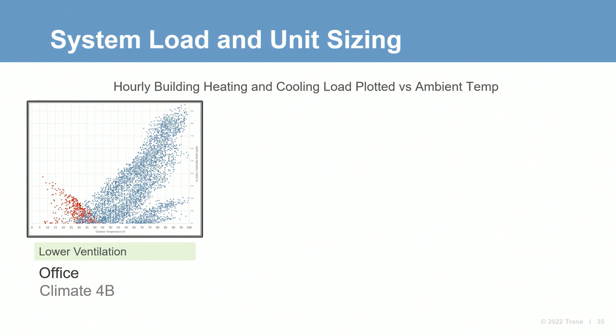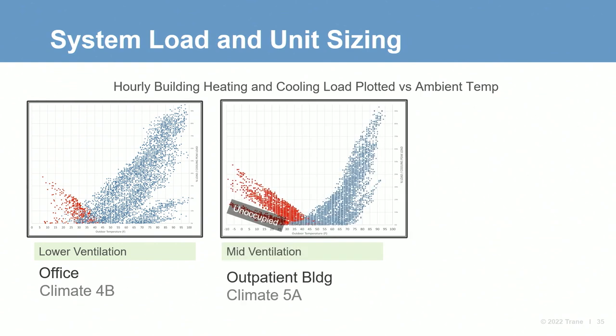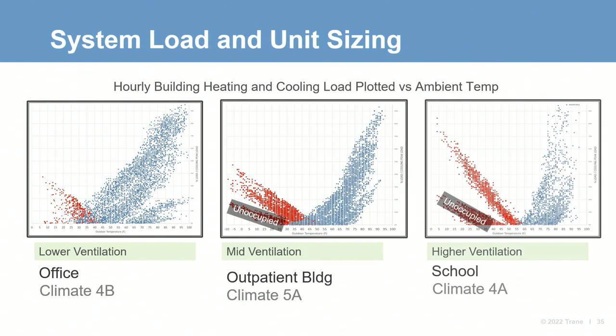Now, let's bring in different building types with different ventilation rates and climate zones and then compare. We'll look at an office building in climate zone 4B, an outpatient building in climate zone 5A, and the school from our first example. First, notice the variation in the difference between the cooling and heating peaks on the plots. The magnitude of the differences varies primarily by ventilation rate. There will be some variation driven by the building type and the climate zone, but it is important to note that the ventilation rate impacts loads much more than building type and climate zone.